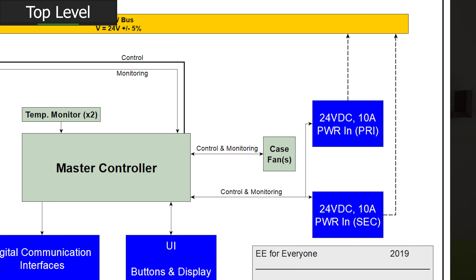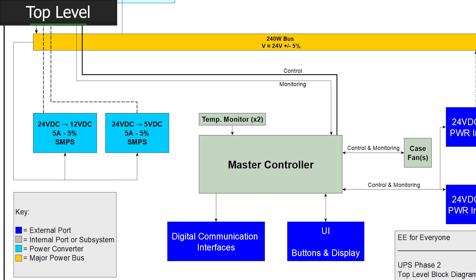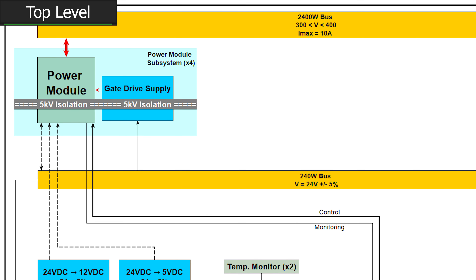We also define the voltage, current, and wattage limits for the two DC buses. These are the supplies that take the 24 volt input and step it down to 5 and 12 volt power for the main board and modules. We added a maximum power draw and define that for each of the daughter cards on these rails, so we can define the minimum acceptable performance for those two power supplies. This is part of a larger system power budget, which reserves at least one amp for each module at each voltage. Our high-level architecture also defines which power buses are bi-directional versus unidirectional — the 24 volt and the high voltage DC bus can actually be sourced or fed to the daughter cards, depending on whether it's a battery backup or an inverter. Finally, there are four power modules shown to have 5 kilovolts of isolation from anything accessible to the user, while also having an interface back to the master controller.